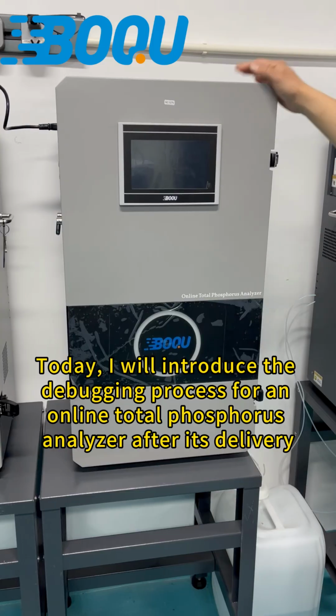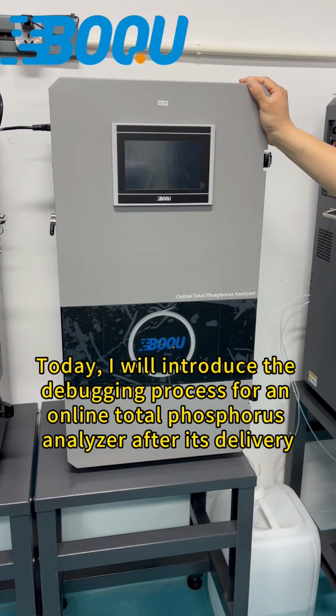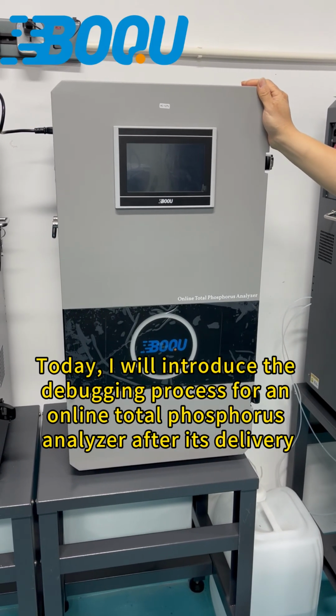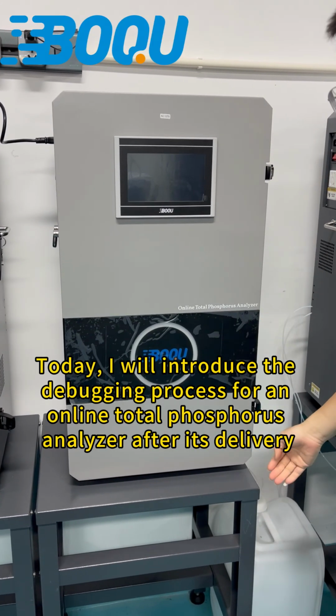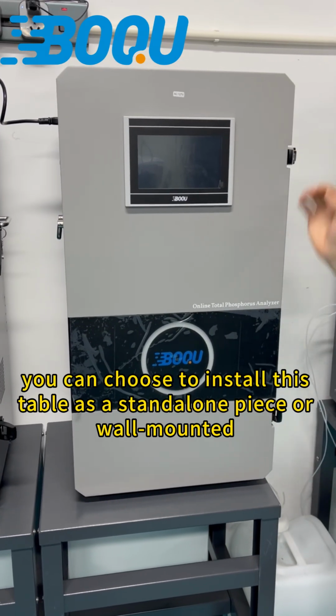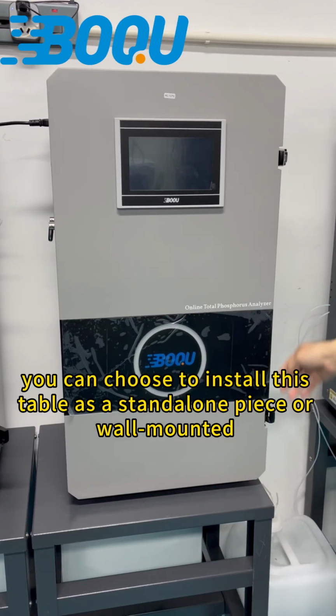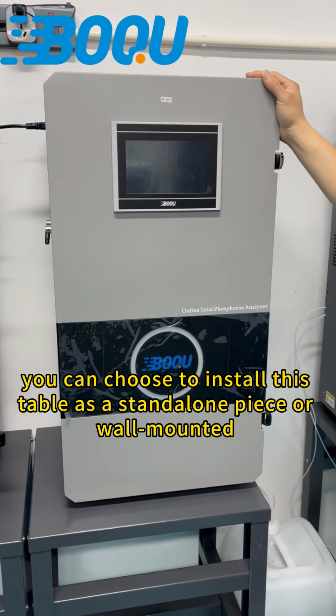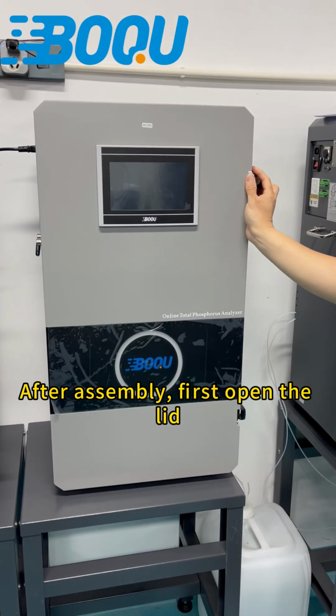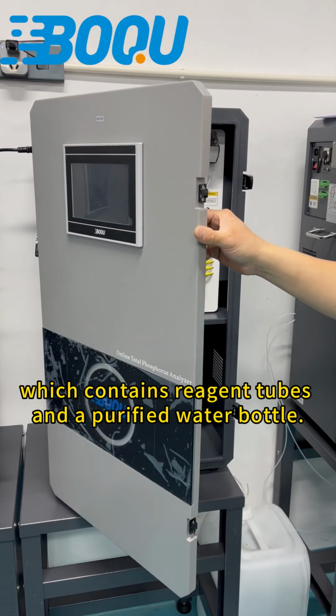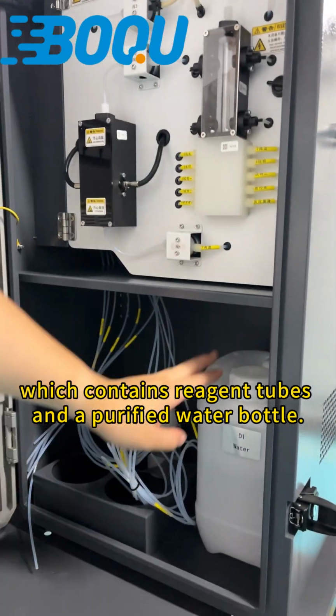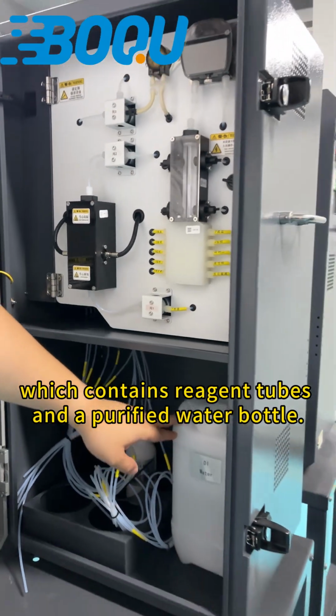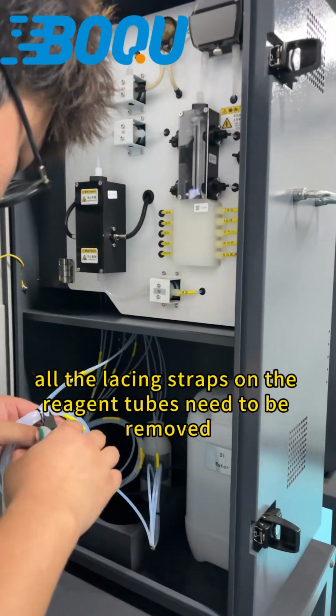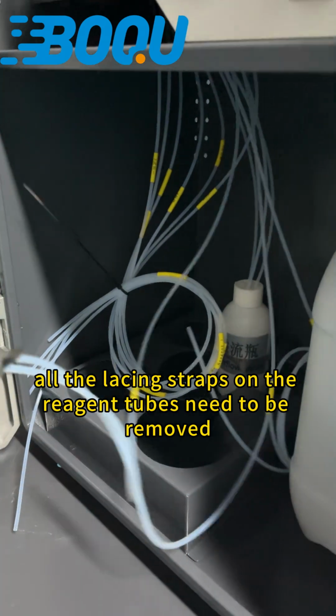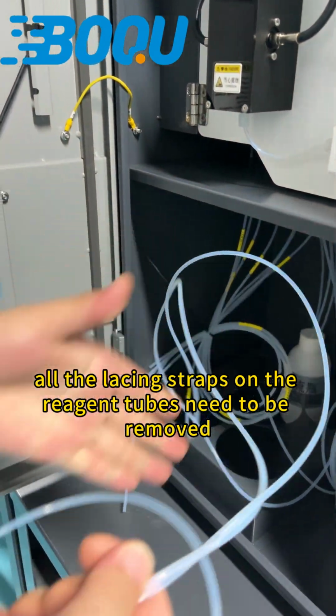Today, I will introduce the debugging process for an online total phosphorus analyzer after its delivery. First, you can choose to install this table as a standalone piece or wall-mounted. After assembly, first open the lid, which contains reagent tubes and a purified water bottle. Next, all the lacing straps on the reagent tubes need to be removed.